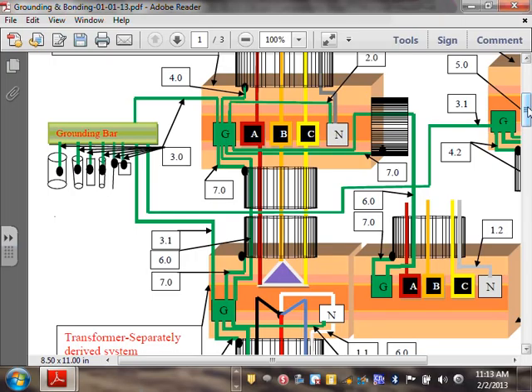You guys are familiar with, if you have two systems, these are typical color code, not code requirement, by the way. A lot of people think it's code requirement, but it's typical industry standard color coding. The only code requirement, by the way, is if you put the 208 system and the 480 system in the same conduit or box, now you have to separate them by system and by phase and by neutral. So that's the only time you have to separate them. A lot of us guys separate them anyway, and you have to have a label on every panel to tell you what the color code is for every system.